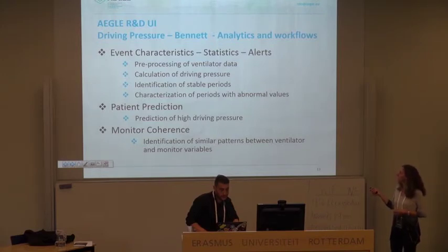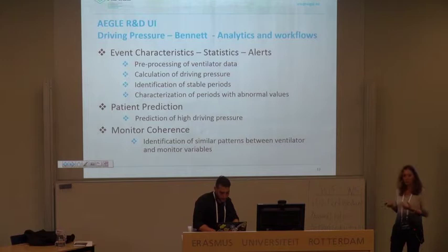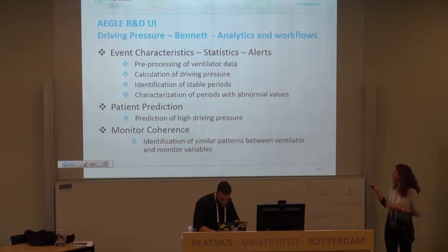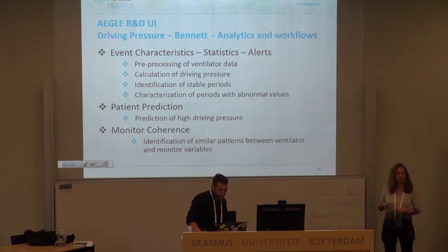And because we want to analyze stable periods, not when something is rapidly changing, because at this point these connections are not so meaningful, we identify the stable periods through our analytics, and we characterize them with some basic statistics, and we further characterize and identify periods with what we have shown to be abnormal values.